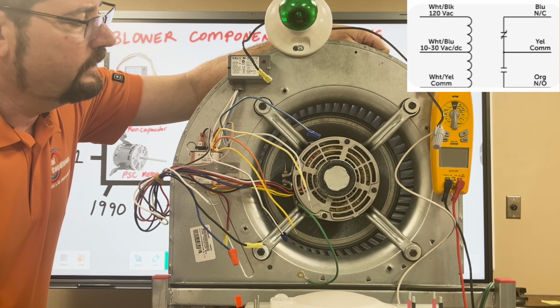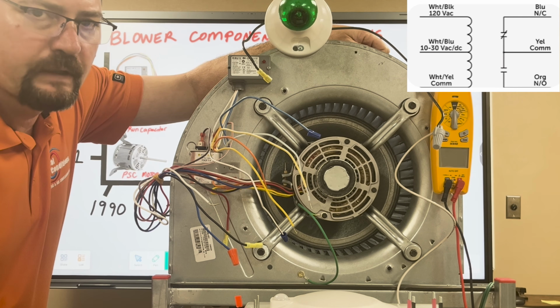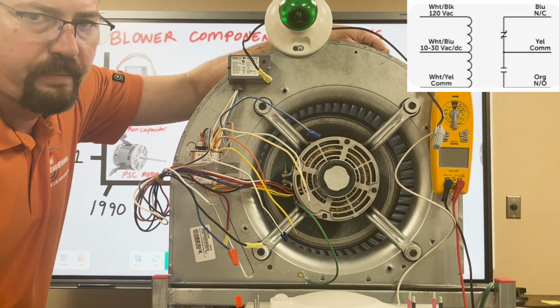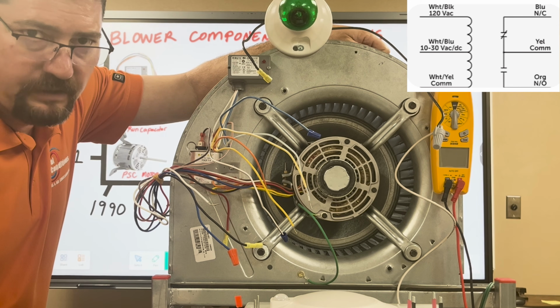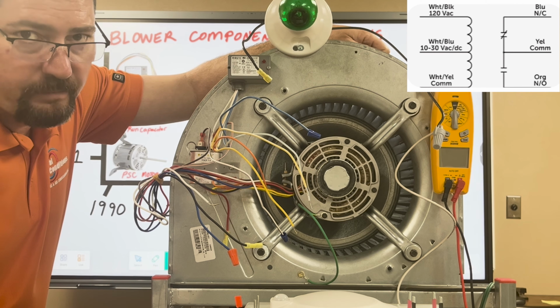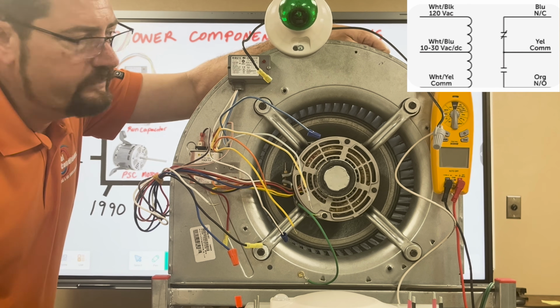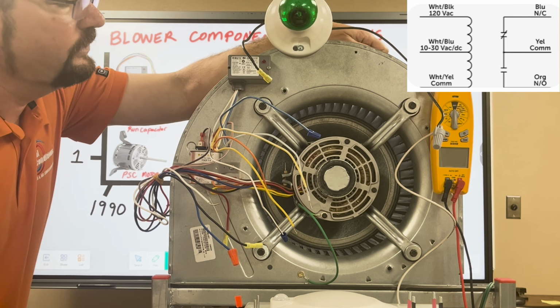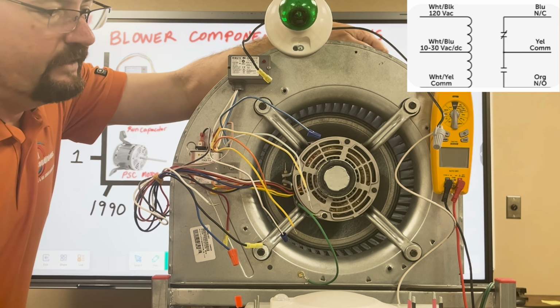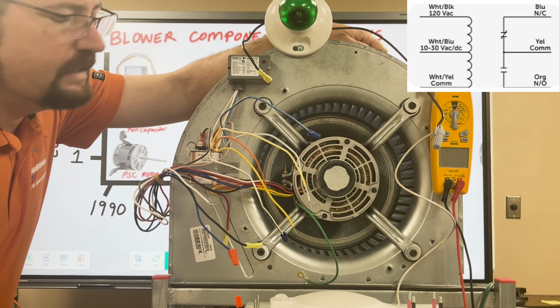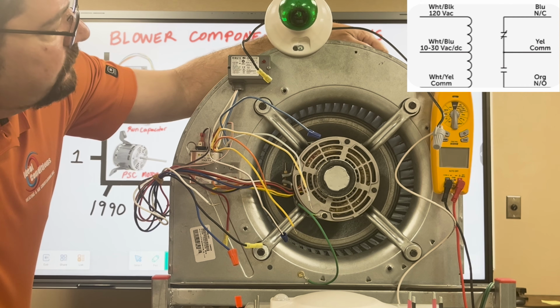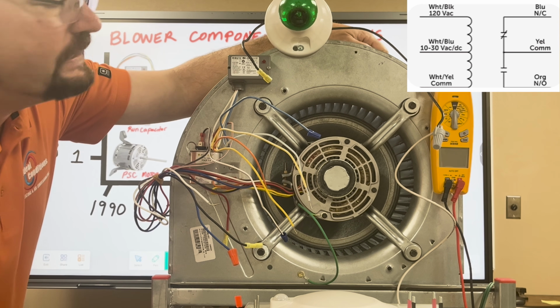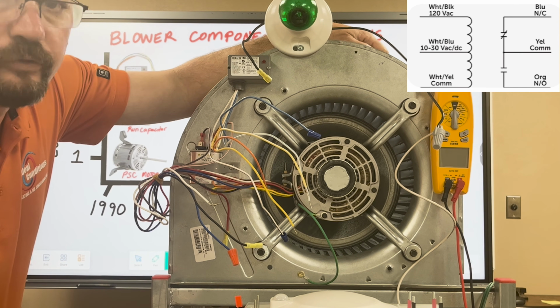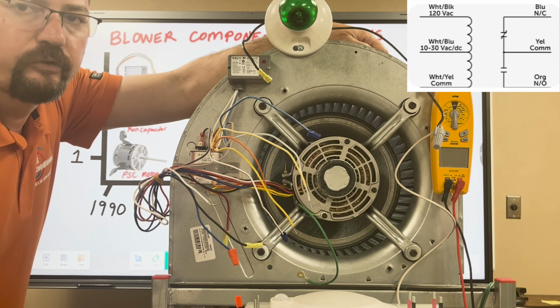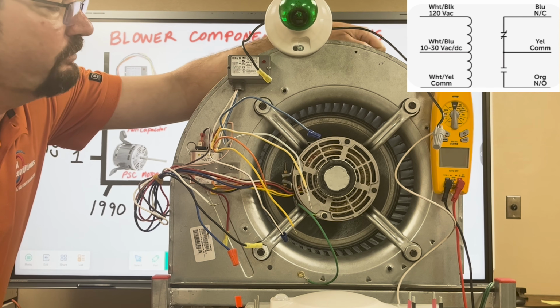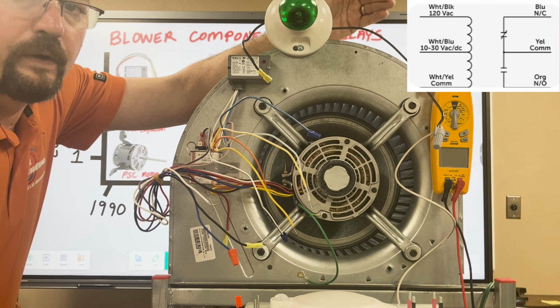It may be there for a lot of commercial applications, but don't walk right past it because it's not that expensive of an item. One of the things that I like about it is its versatility and diversity on a job site, meaning you can use it for different coil voltages. If I had 12 volts DC, not 9 volts DC, I backed that up, 12 volts DC, if I had 24 volts alternating current, or 120 volts alternating current, and that was my only voltage that I can use for the coil, I can do that.